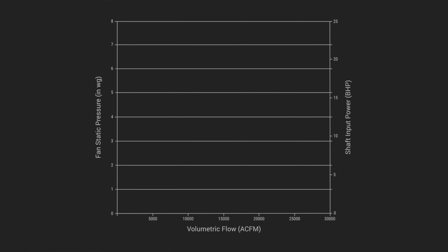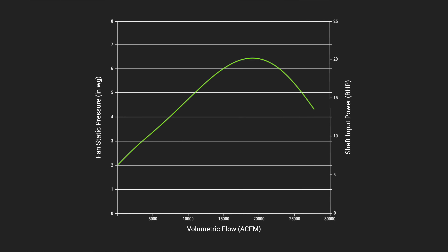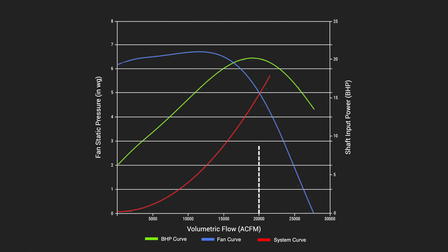A fan curve also shows the amount of power a fan uses when running at a given operating point. This data is represented as another curve called the brake horsepower curve. To determine power consumption at a given operating point, follow the intersection of the fan curve and system curve to the corresponding point on the brake horsepower curve, then straight across to the secondary y-axis on the right.